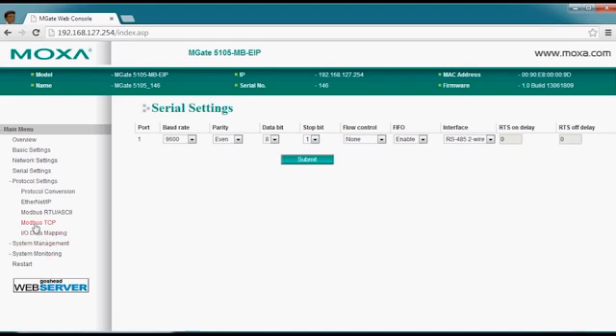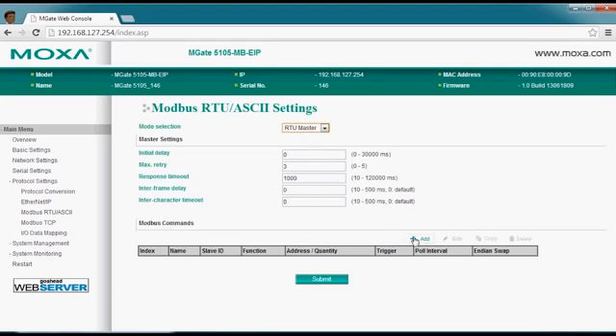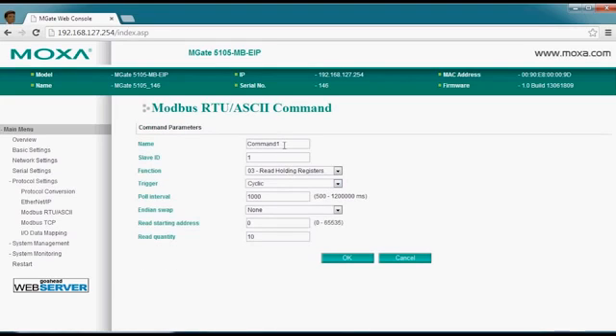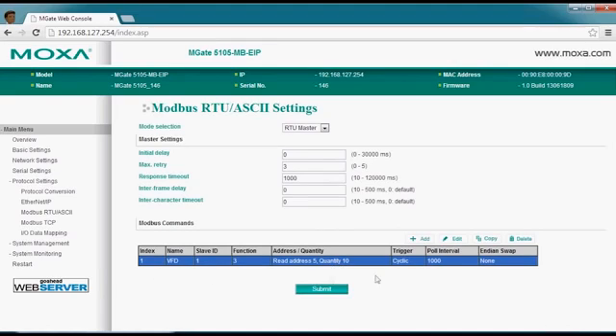Once we've done that, we'll go ahead and define the values we want to look at from the PLC. So we'll click on Modbus RTU. Here we know that the MGate is going to be a master, and we're going to add some registers to pull. Let's call this the VFD — we're going to read some data out of it, starting from register five, reading 10 registers, and we'll submit these for a polling cycle. You can see it will poll this data every 1,000 milliseconds, or one second — you can change that if you prefer.